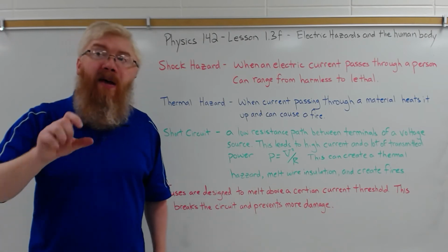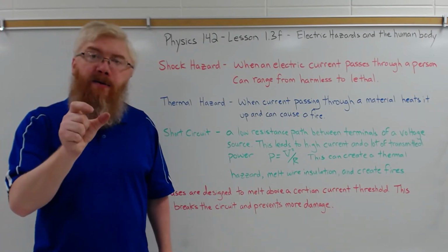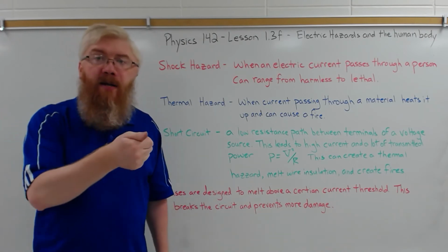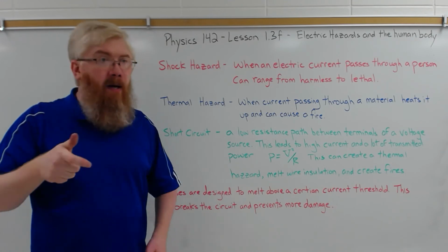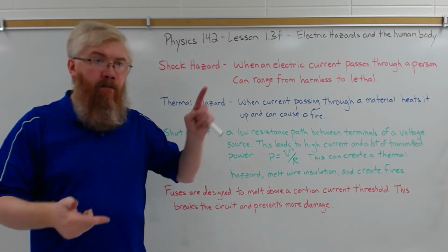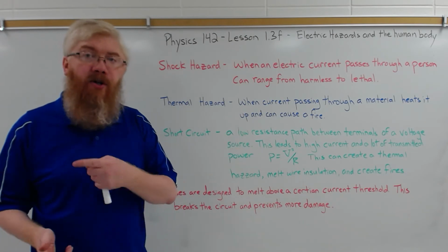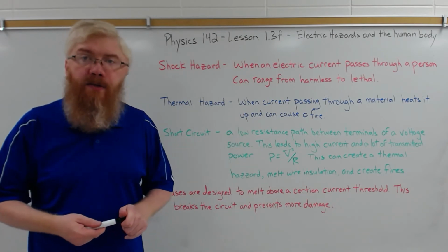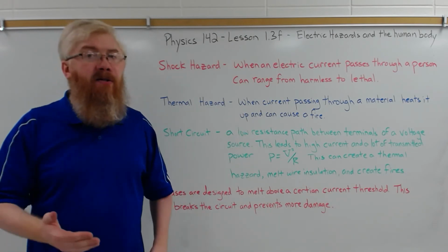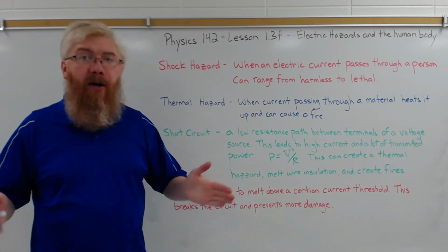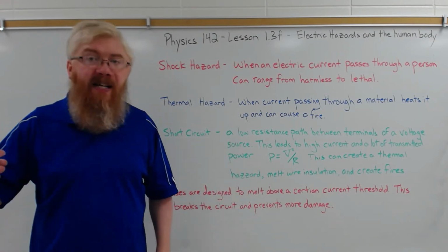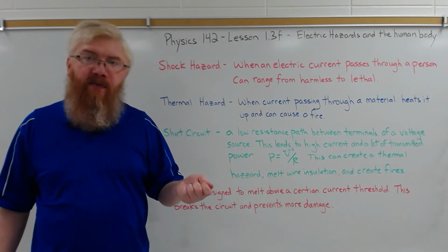So if you blow a fuse, if a fuse melts, do not just remove it and put in a new fuse, because that will complete the circuit. More of the current that was running through there is going to run through there again and melt the second fuse. If a fuse melts, you have too much power on that circuit, or you have a short circuit somewhere. Fix it before you replace the fuse.